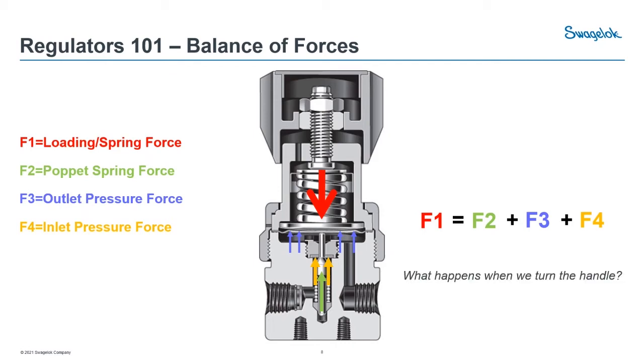What happens when we turn that handle and how does this balance of forces actually work? As we turn the handle down, we compress the spring, which increases our spring force. Something on the right side needs to compensate and balance for that. We've already selected our poppet spring, so that shouldn't be moving, and our inlet force is constant. So that forces our outlet pressure force to increase — and that's how our regulator actually works.